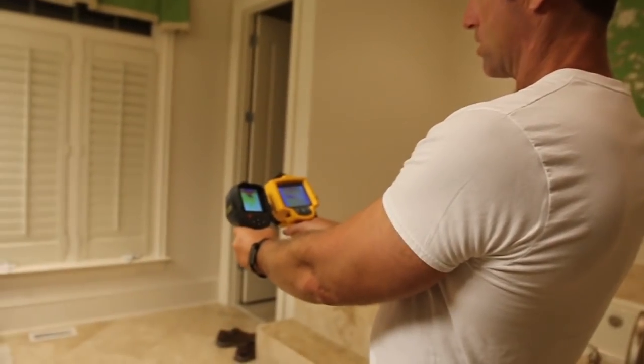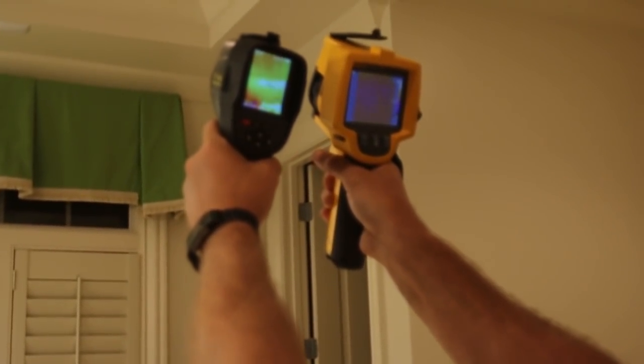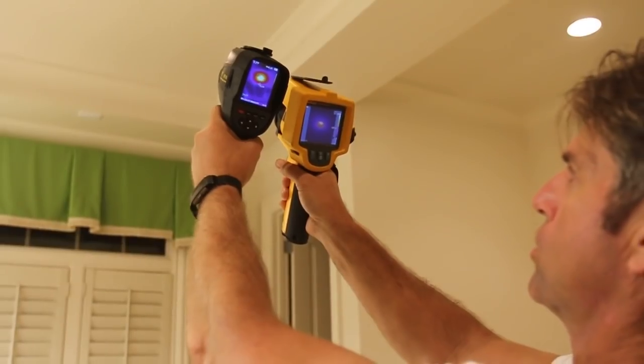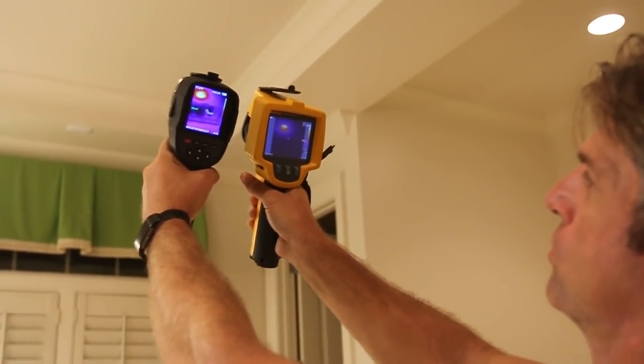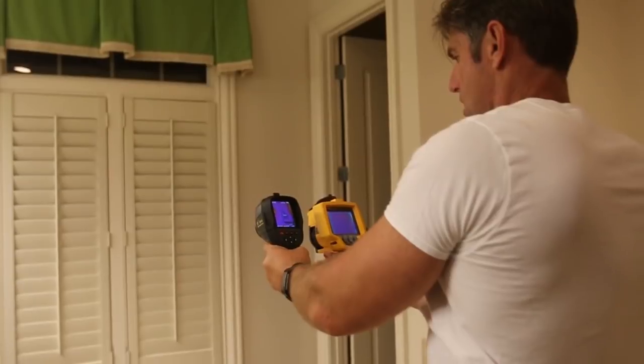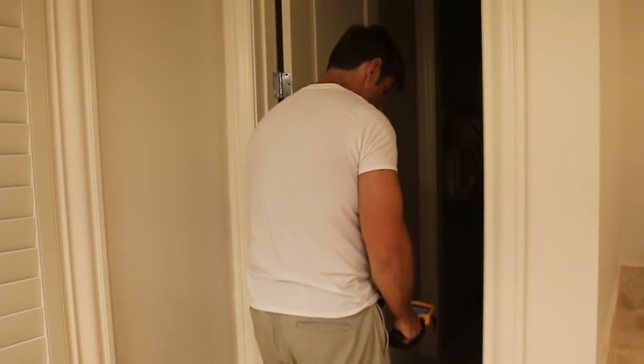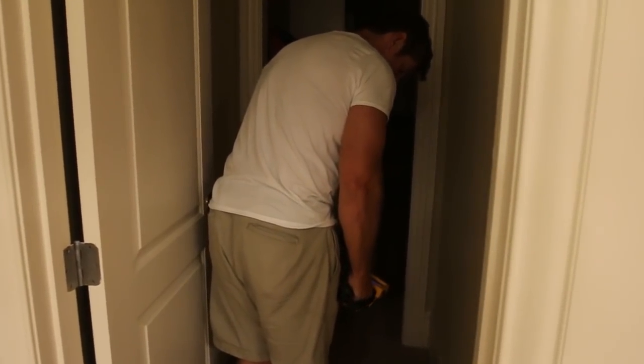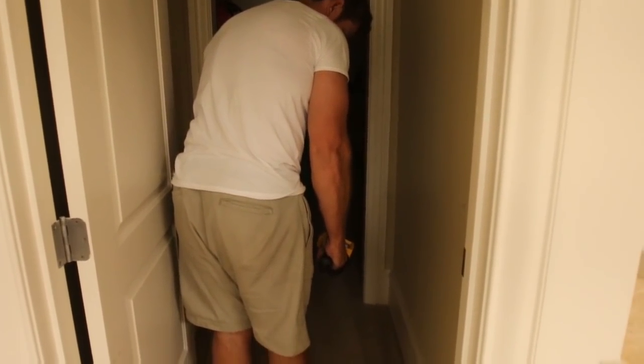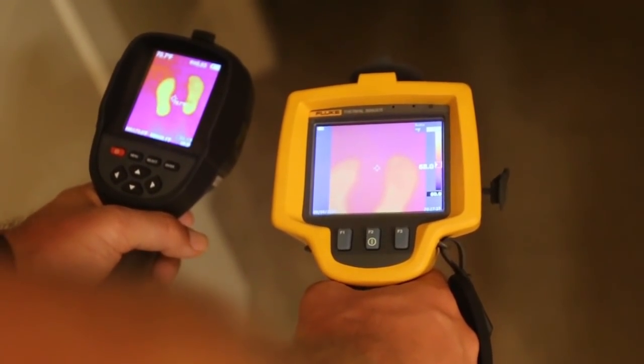We've got the air conditioner on, coming out of the vent there. You can see the windows — obviously it's going to be really hot up there at the light. It's showing you the actual temperature side by side. My Fluke is 125 by 125 and the HT18 is 160 by 320 I think. Let's do the foot test or hand test. I'm going to walk in here and we're going to see how my foot heats up. You can see how hot my foot is, and obviously if I take my foot away — it's a pretty good test. I'm going to give it to the new, less expensive one. It has a lot better resolution.